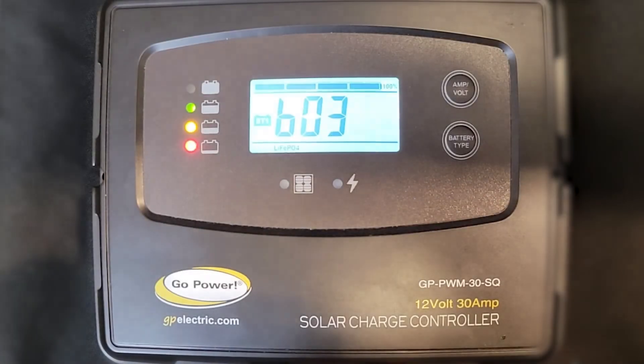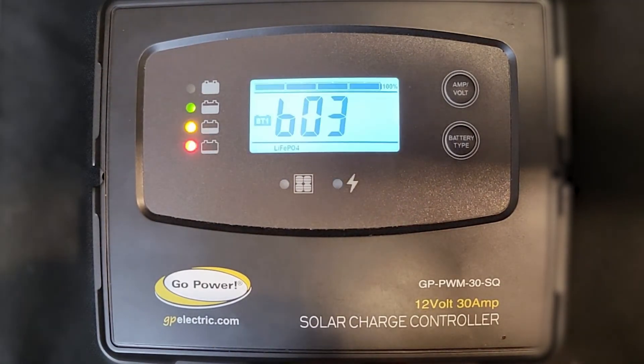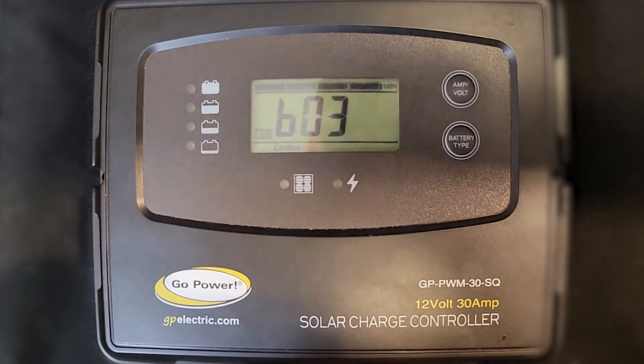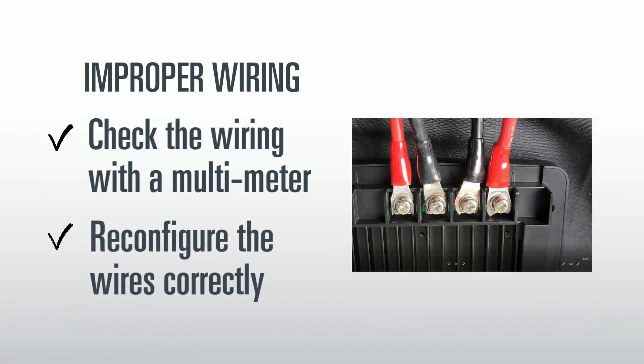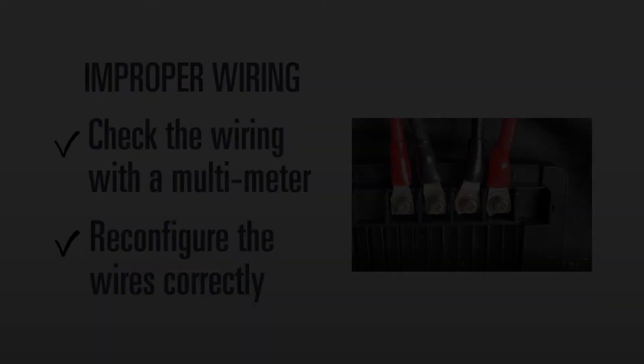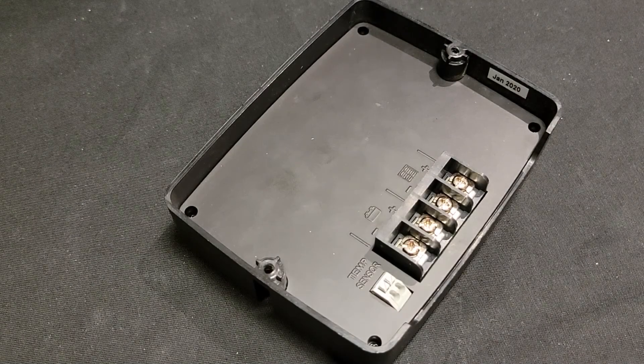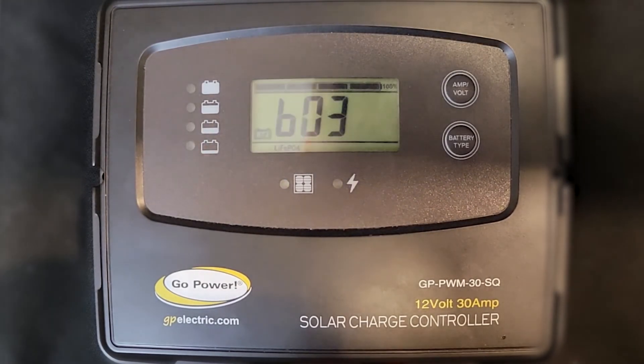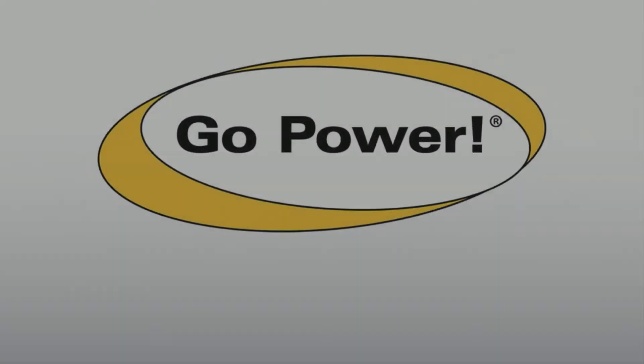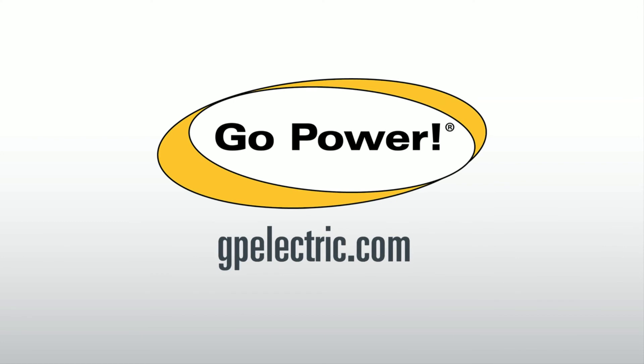There have been instances where the solar wires have been placed in the battery connections on the solar controller, and the b03 error code would show in this instance as well. Check on the back of the controller with a multimeter to confirm the charging sources. If it has been wired incorrectly, swap the wires to the correct position. There are labels on the back of the controller to indicate the correct positions. If you complete these steps and your controller is still showing the error, contact Go Power technical support for additional steps. Contact info is included in the description below.